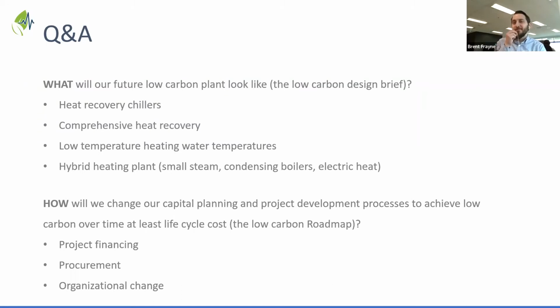I'm just bringing the presentation, but we do see a big shift towards geothermal. The use of geothermal in healthcare facilities, obviously, but Corner Brook Acute Care was a project that we're working on that didn't have a mandate to go net zero carbon, but had some issues with fuel supply and reliable natural gas or propane. All they had was number 2. And when you look at what options are available to you to be able to meet the heating and cooling loads of a building like a large acute healthcare facility, you're not left with many other options, right? Brent, you said that was Corner Brook, Newfoundland? That was in Corner Brook, yeah, the acute care facility there.